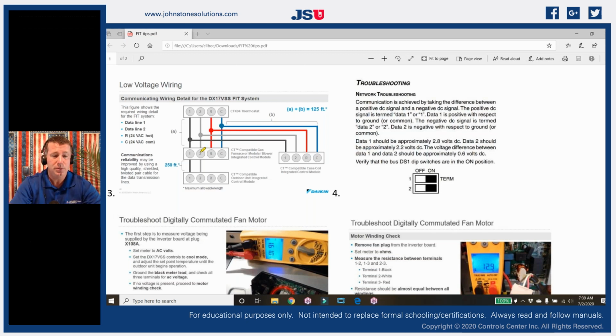So we're going to communicate on number 1 and number 2. We're pretty much going to be starting at our furnace and our air handler. We're going to be tying it to number 1 and number 2 at our thermostat, at our coil, and at number 1 and number 2 of our outdoor unit. And that's really all the communicating network is going to do.